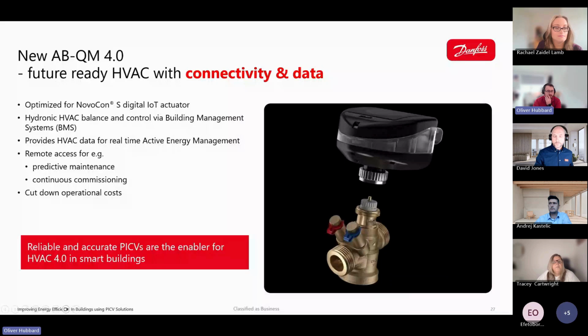So the ABQM 4.0 is designed specifically to optimize the performance of the Danfoss NovoCon actuators, and it creates a fully integrated intelligent valve solution. It establishes perfect hydronic balance while simultaneously connecting that balance out into the BMS system. So we're not just controlling flow, we're making it visible and measurable as well. It provides the BMS with HVAC data, which allows real-time active energy management for 24/7 energy optimization, allowing continuous optimization rather than periodic adjustments. And with remote access, there are other capabilities such as predictive maintenance and continuous commissioning. Issues can be identified early, performance can be fine-tuned over time, and unnecessary site visits can be reduced as well, which is just overall lowering operational costs.